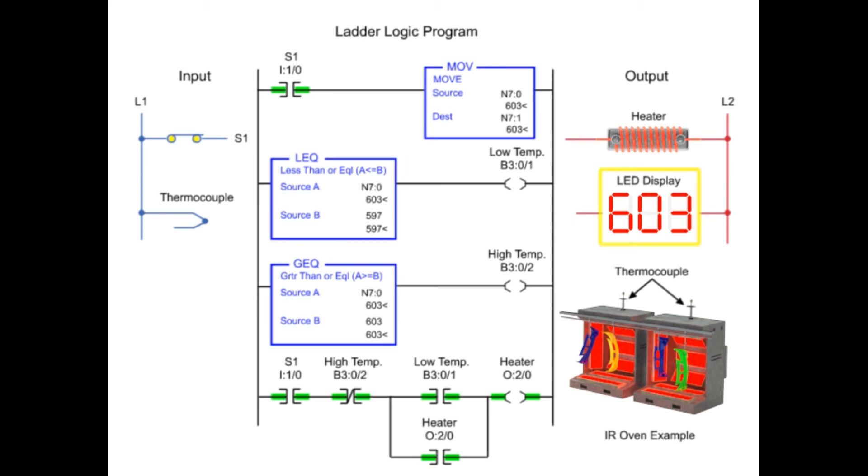Reaching 603 degrees or more, the high temp output is enabled since source A is equal to source B of the greater than equal to instruction. When the high temp output is true, the heater turns off and remains off until the temperature reaches 597 or lower.